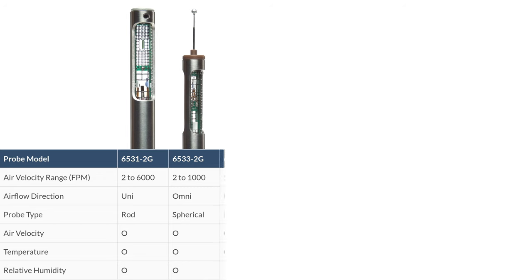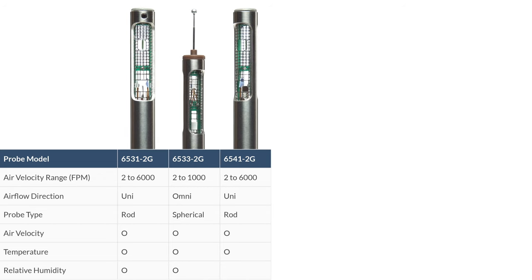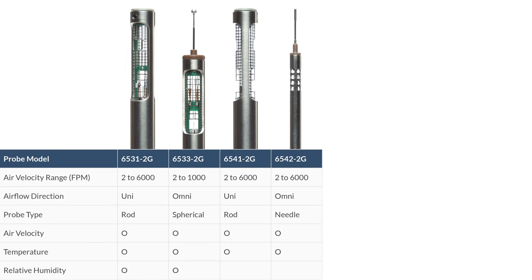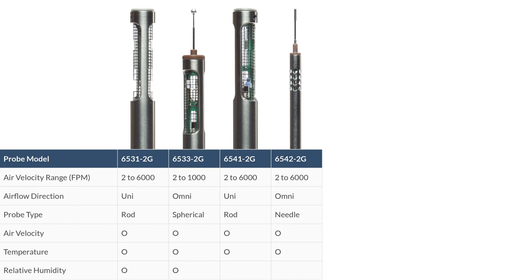Probe model 65412G is a unidirectional rod-type probe capable of reading air velocity and temperature within an air velocity range of 2 to 6,000 feet per minute. Probe model 6542-2G is an omnidirectional needle-type probe capable of reading air velocity and temperature within an air velocity range of 2 to 6,000 feet per minute.